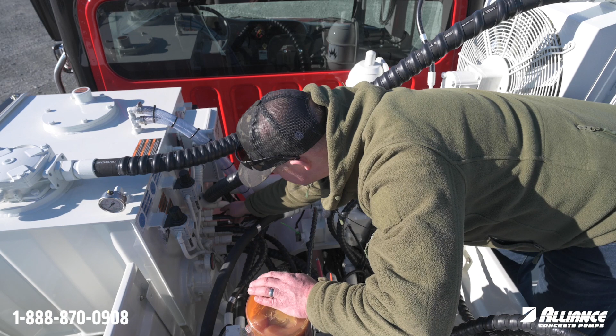The fan also has a sensor on the hydraulic tank, there's a sensor with a little angle plug here, square plug. This is what's called a 55-degree sensor. So that sensor will turn the fan on no matter what at 55 degrees Celsius. Below that sensor there is a 90-degree shutdown sensor that will shut down your pump and your accumulator pressure, so you cannot pump if the hydraulic oil overheats past 90 degrees Celsius.